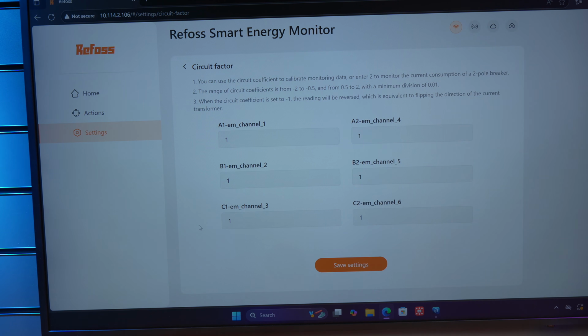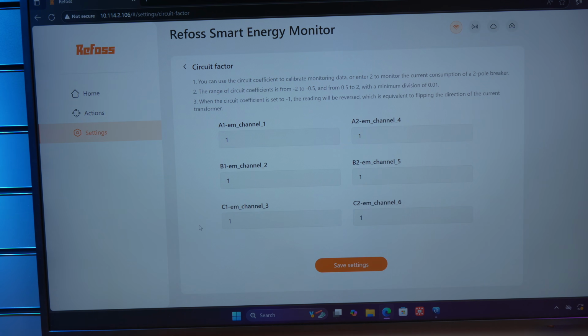By default, they're all set to 1, but if you had a CT installed the wrong way round, all you need to do is change that channel to -1 and that'll flip the values around. You can also set this to different values here to slightly tweak the numbers to calibrate it, or what it says up here, to enter 2 to monitor the current consumption of a 2-pole breaker.